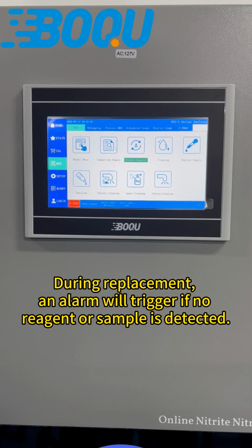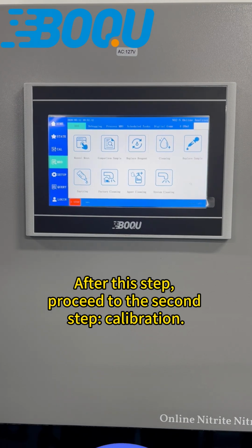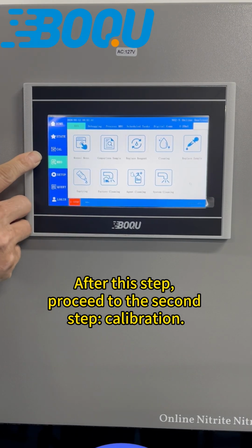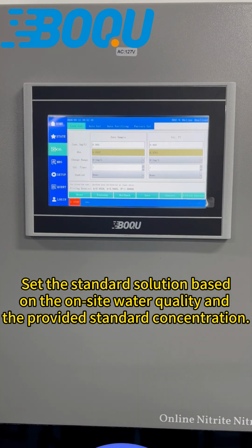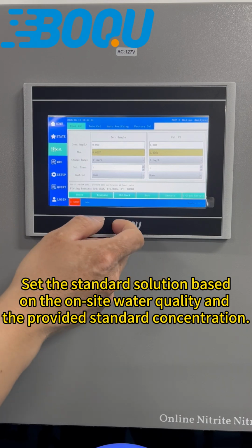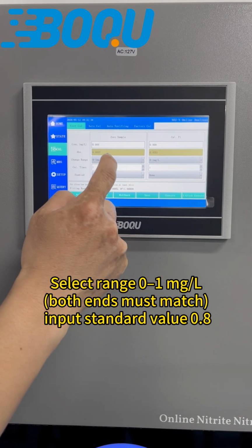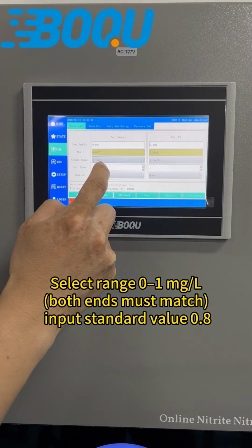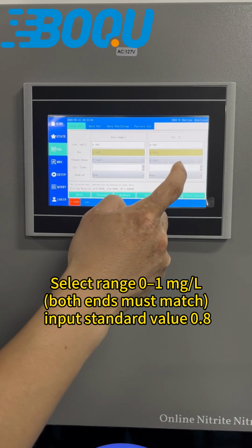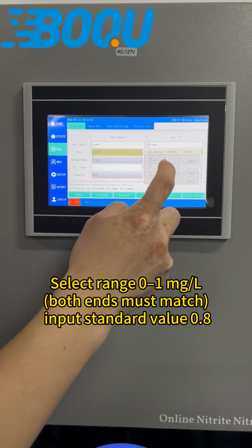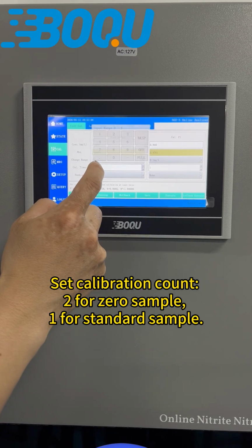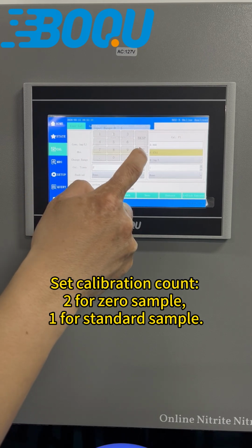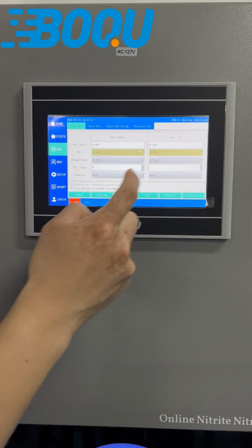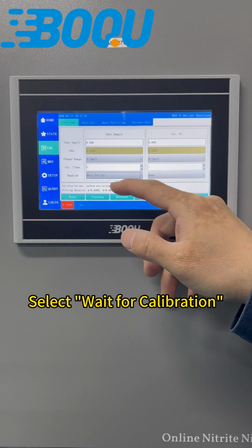During replacement, an alarm will trigger if no reagent or sample is detected. After this step, proceed to the second step, calibration. Set a standard solution based on the on-site water quality and provide a standard concentration. Select range 0 to 1 milligrams per liter. Both ends must match. Input standard value 0.8. Set calibration count 2 for 0 sample, 1 for standard sample. Select Wait for calibration.